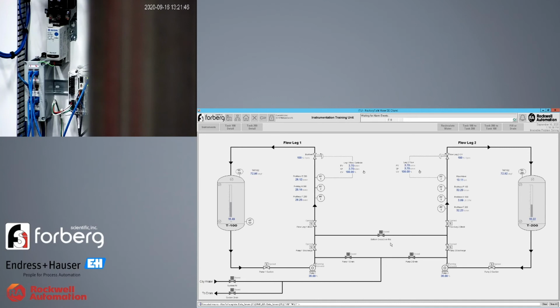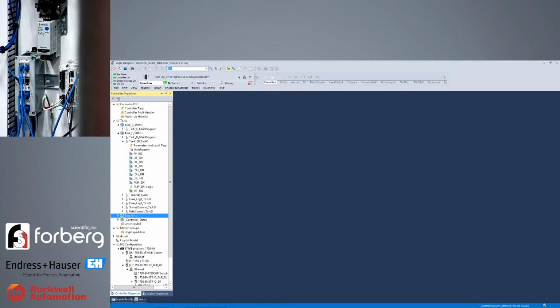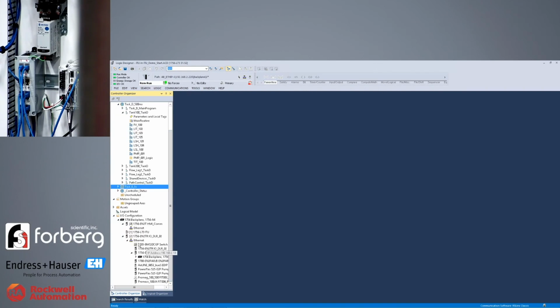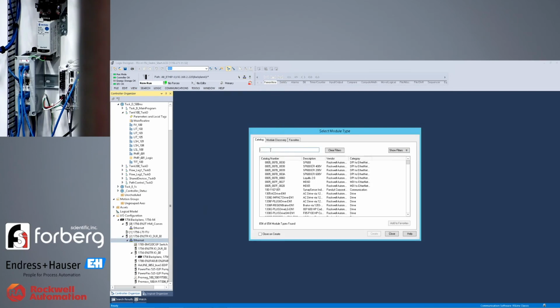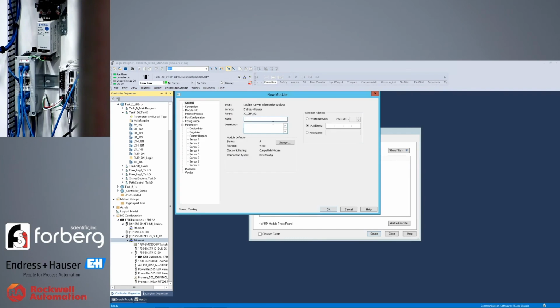To save time, I already have Studio 5000 development environment open, and I will add the Liquiline through the add-on profile. So I select the appropriate add-on profile to match our device. And when it pops up, I need to give it a name. Then I need to put in the appropriate IP address for the device that's already configured in the field.